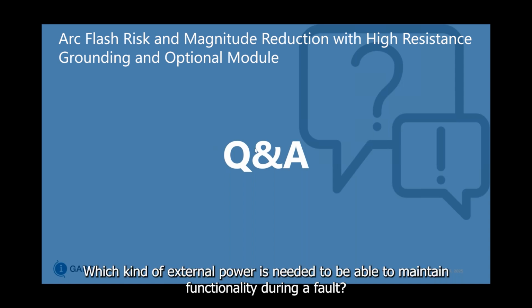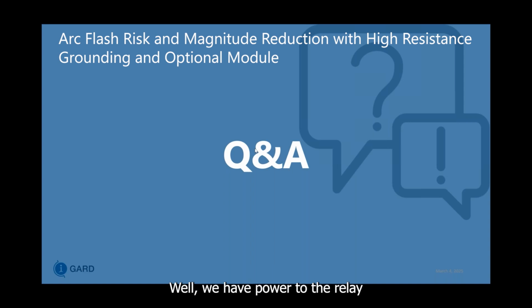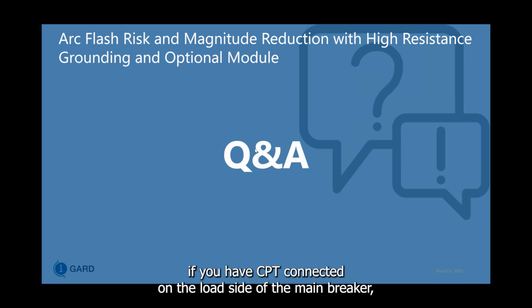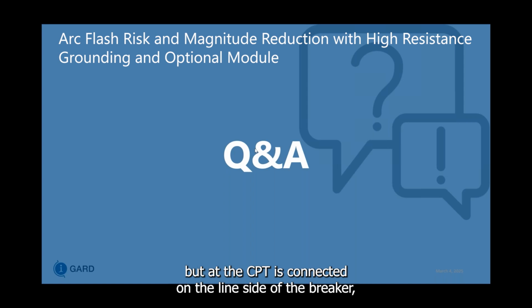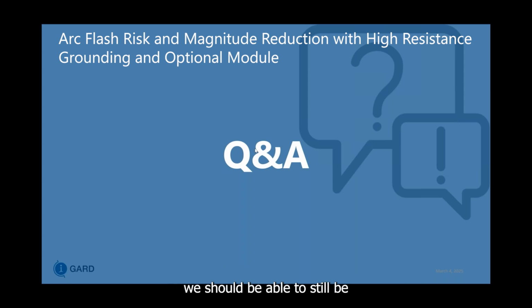What kind of external power is needed to be able to maintain functionality during a fault? Well, we have power to the relay, and when the fault occurs, we will be tripping the upstream breaker. Depending on how the relay is powered, breaking open of that main breaker may cause the relay to shut down if you have CPTs connected on the load side of the main breaker. But if the CPT is connected on the line side of the breaker, we should still be able to pick up the fault scenario.